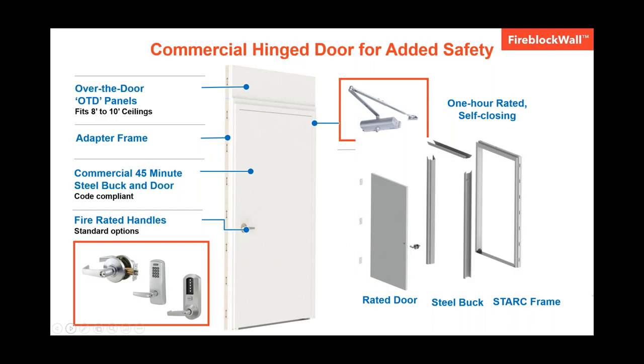Our door has a 45-minute rating and is self-closing, meeting NFPA and IBC code requirements. There are three components that make up our door. The first is the STARC adapter frame, which mates with our panels on both sides with the simple lift and drop connection. Then the knockdown steel buck frame is installed inside the STARC frame, and then the door is hung. The door itself is seven feet tall, 48 inches wide with a 39-inch clear opening. The buck itself can be flipped so the door can swing either in or out. The handle set and closer are one-hour rated, and we offer multiple lock options depending on the security your job requires. We also have over-the-door panels that allow you to create a fire rated seal from the top of the door to the top track.